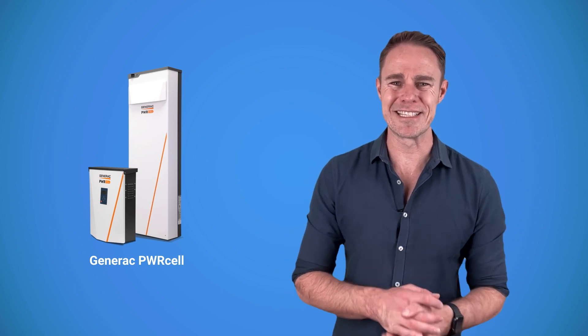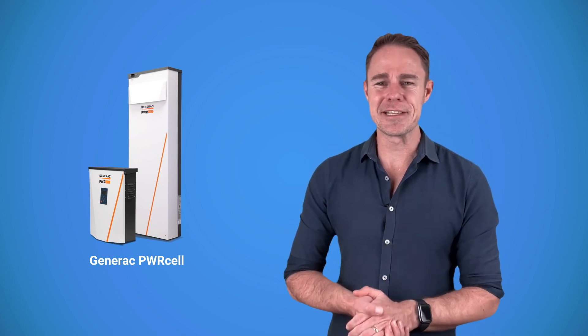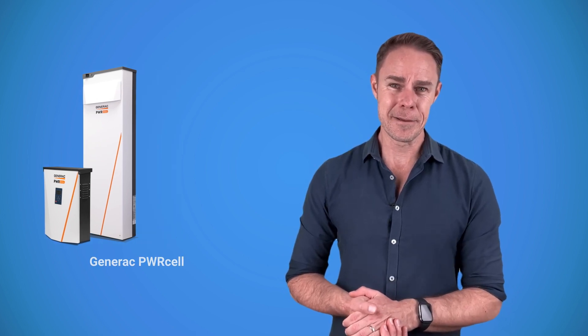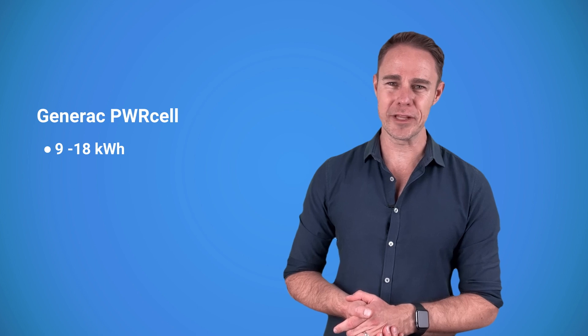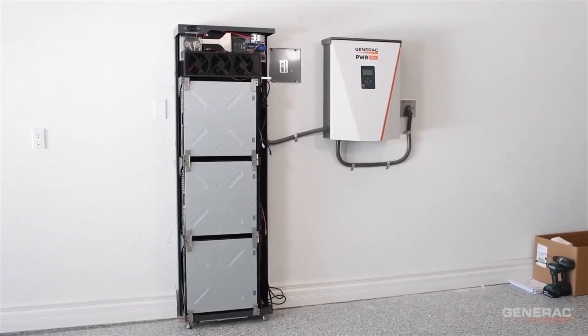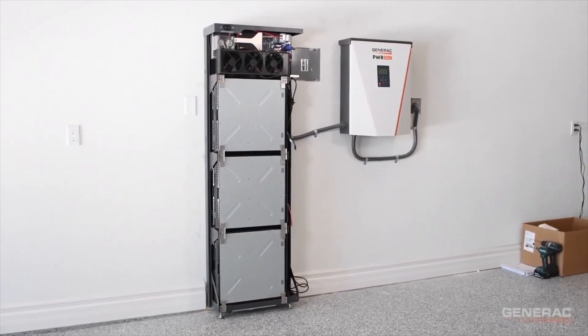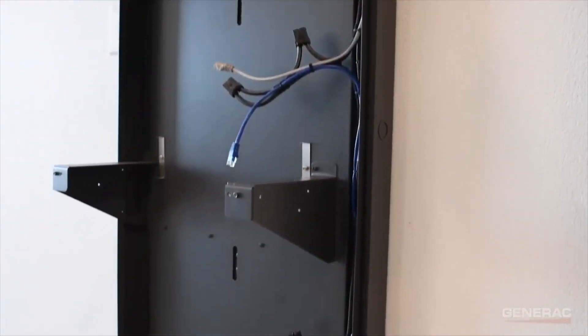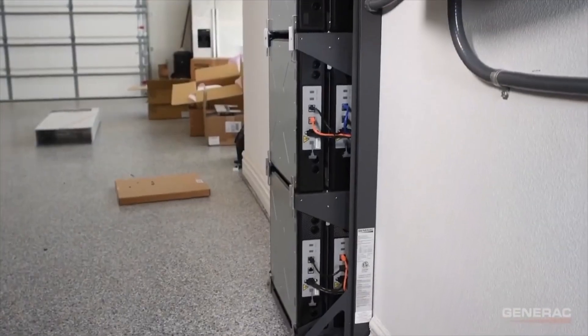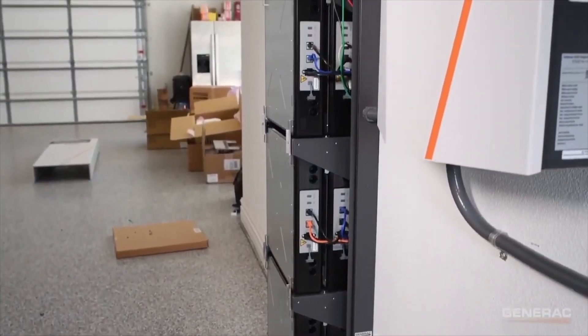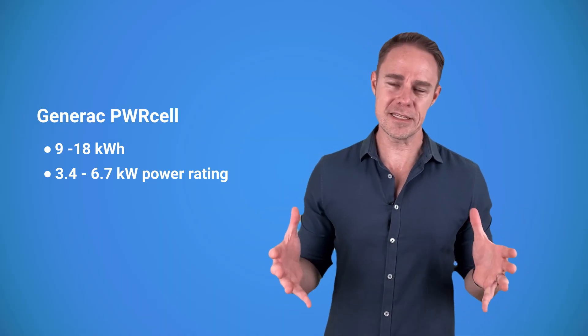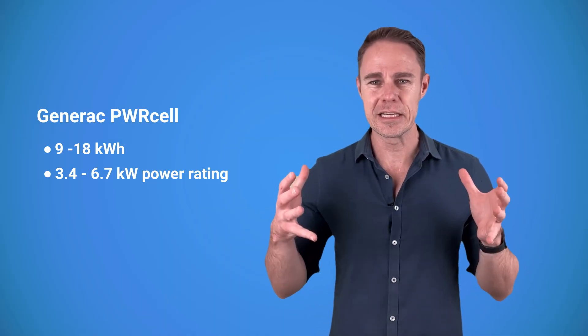Next, we have Generac PWRcell. Now, this system consists of a cabinet with three to six battery modules in it. The minimum capacity is nine kilowatt hours and each battery module increases it by three. You can get 18 kilowatt hour capacity with a single cabinet and the power ranges from 3.4 kilowatts to 6.7. Of course, depending on the number of battery modules. If you want, you can get two cabinets and increase the overall capacity to a maximum of 36 kilowatt hours.